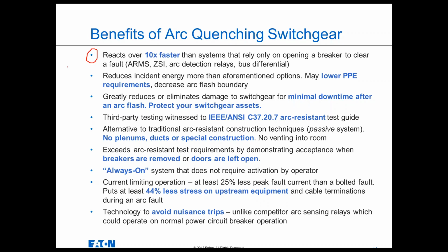Arc quenching switchgear is also a current limiting system. So unlike, as Chris explained, crowbar or bolted fault systems, which are very high-speed systems for quenching arc flash, but when they operate, they apply a zero impedance fault, or practically zero impedance fault. So they draw peak fault current, which, as Chris explained, can damage your upstream power distribution equipment. This system actually introduces some impedance, so it reduces peak fault current by at least 25% when compared to a bolted fault or a crowbar system. And since electromechanical forces are related by the square of the current, it actually reduces the stress on the power distribution system when it operates by at least 44%. And I've seen the stress be reduced by as much as 60% compared to a bolted fault system.